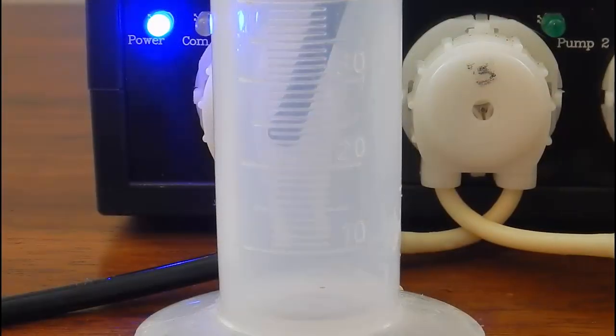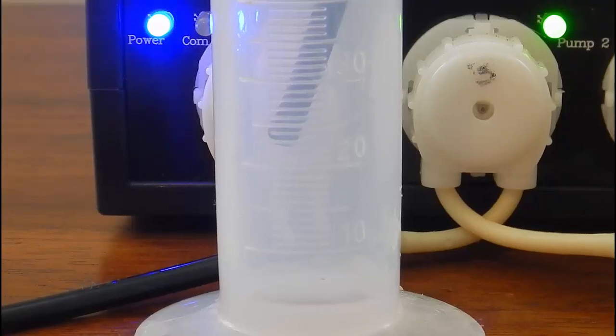Okay guys, once you have everything calibrated, it's good to come in here and test to make sure everything is correct. The pump's going to go off in about 7 seconds. I have it set to do 20 milliliters, so we're going to go ahead and see if this pump is good to go. Alright, just kicked on.